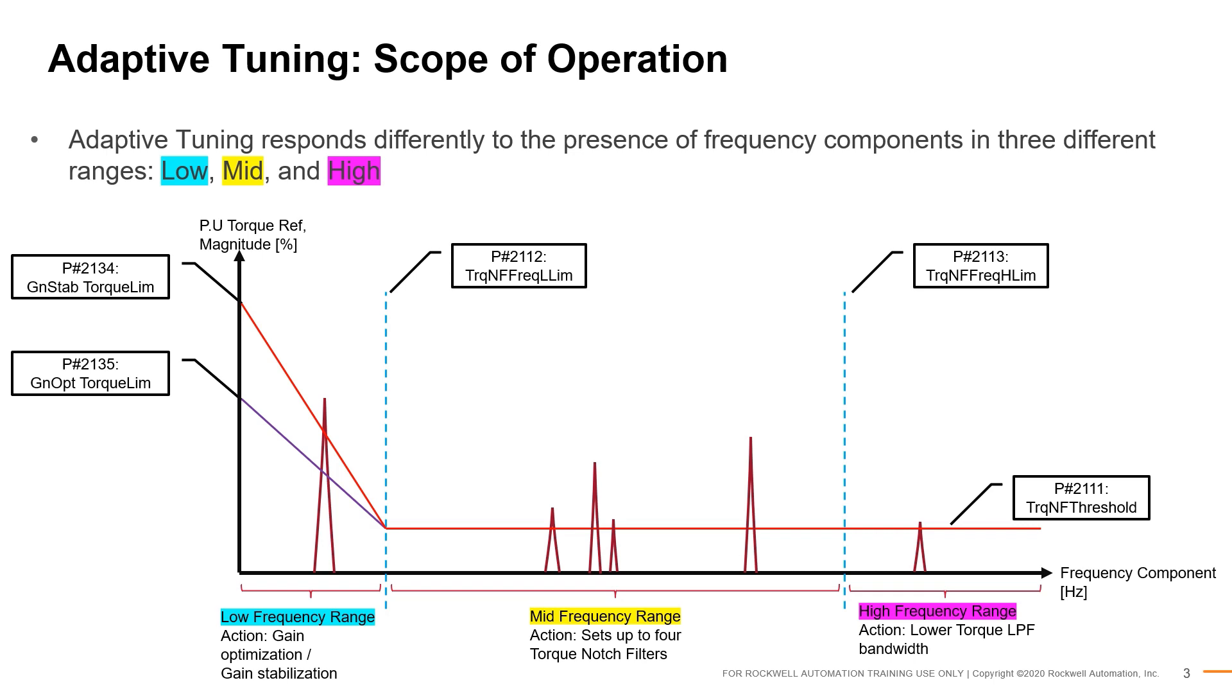The three frequency ranges can be configured using parameter number 2112 and 2113, while the thresholds in a unit of percent torque are configured using parameter numbers 2111, 2134, and 2135. All of the adaptive tuning configuration parameters can be found under the adaptive tuning subsection of the torque parameter family.